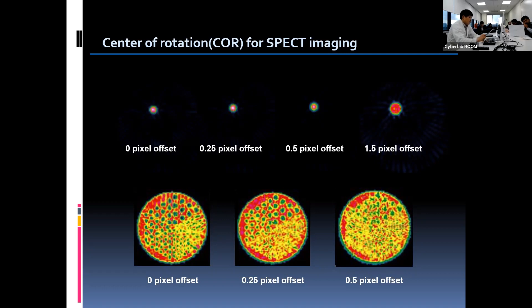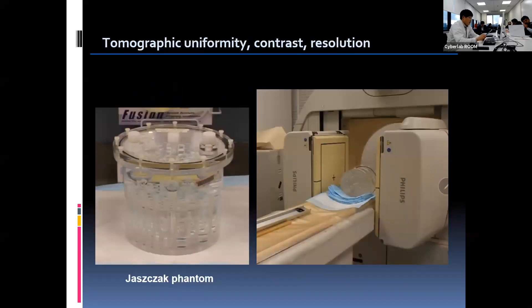COR testing is generally required to be completed once a month. And let's move on to the SPECT phantom study. We especially perform cylindrical tomographic phantom tests to check the performance characteristics of the SPECT imaging system, such as tomographic uniformity, contrast, and resolution.